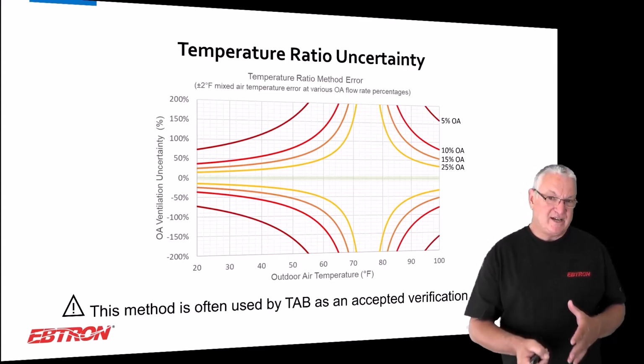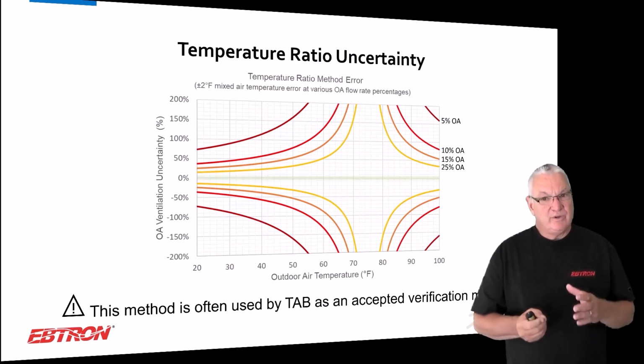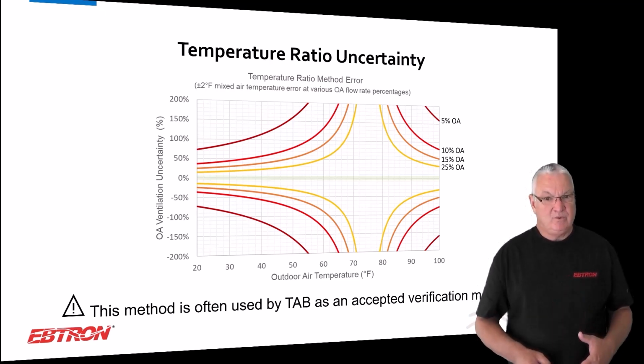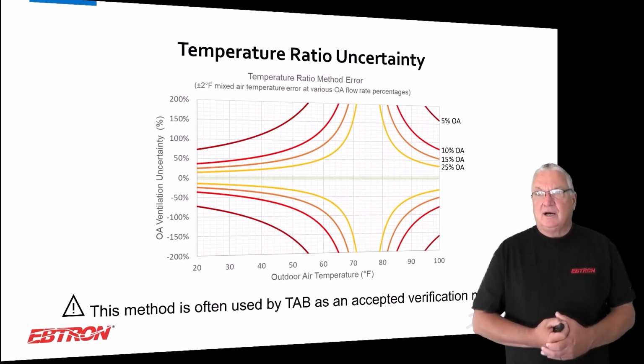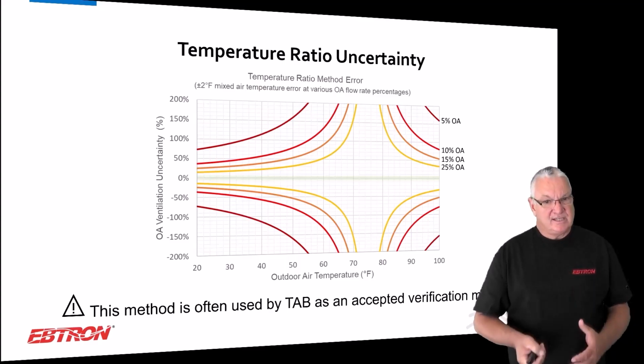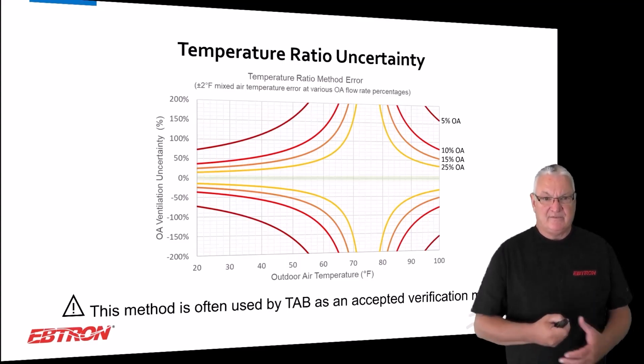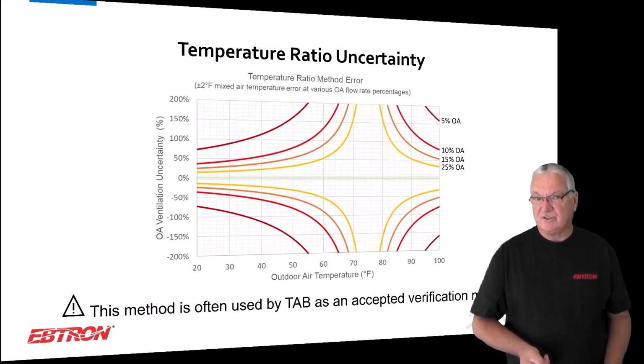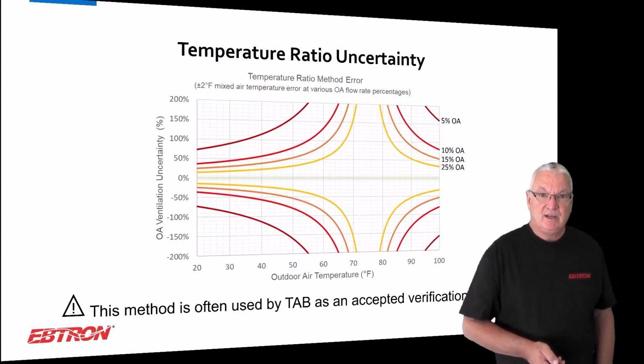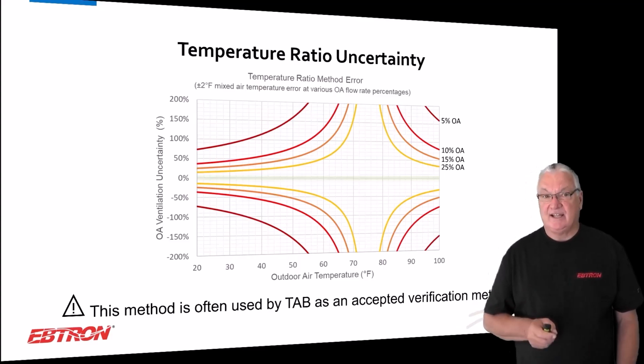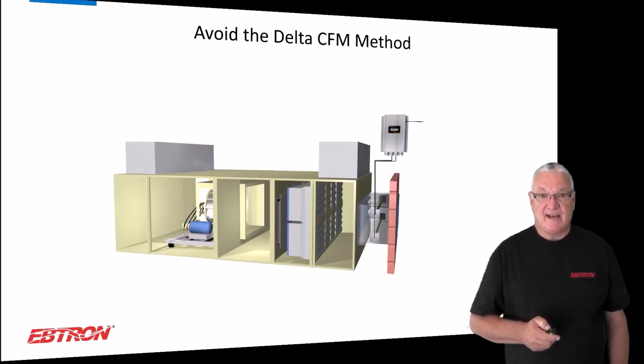The couple of things you've got to get out of this: one, if you were using this as a control strategy, meaning you weren't using test and balance to do it, there's going to be a lot of error. If you were using test and balance to verify something like our piece of equipment, you'd have a lot of error. There's no way it's going to match. So you have to understand that. That method is, to me, out.